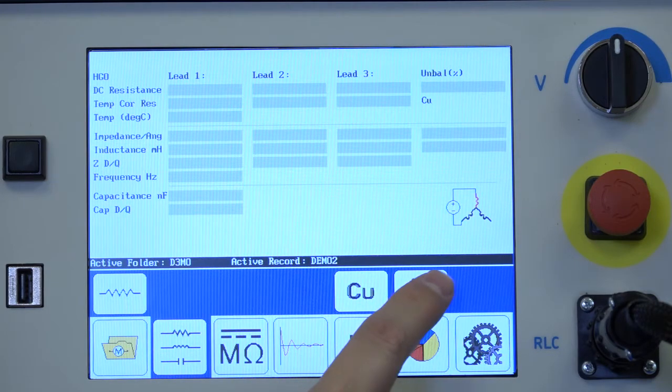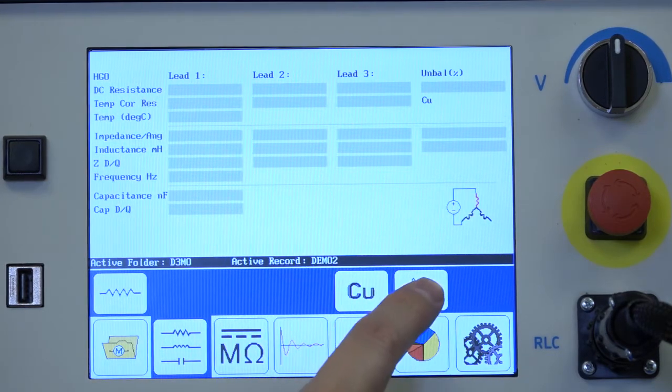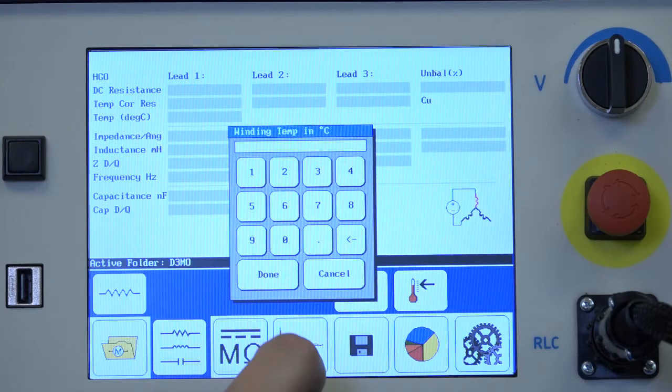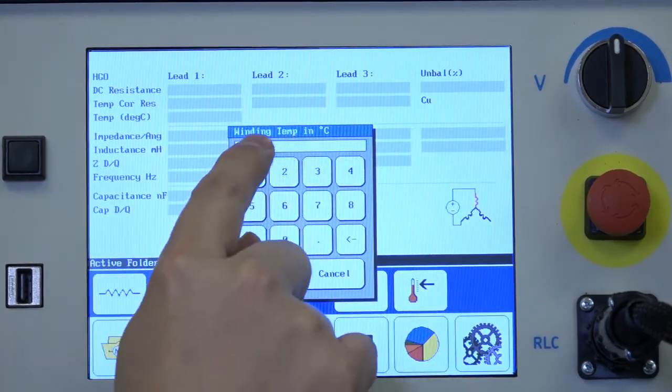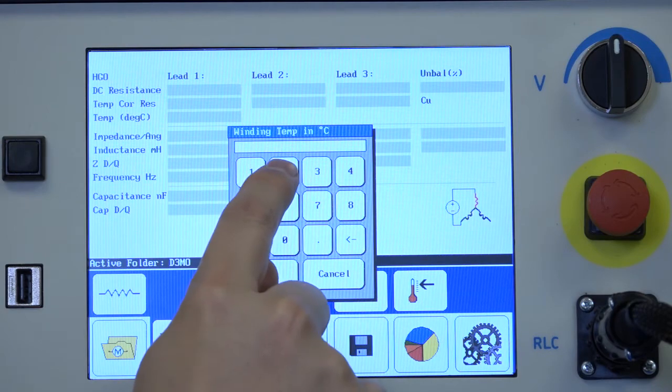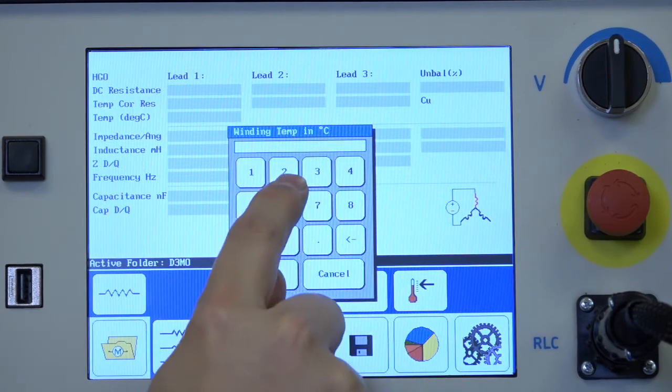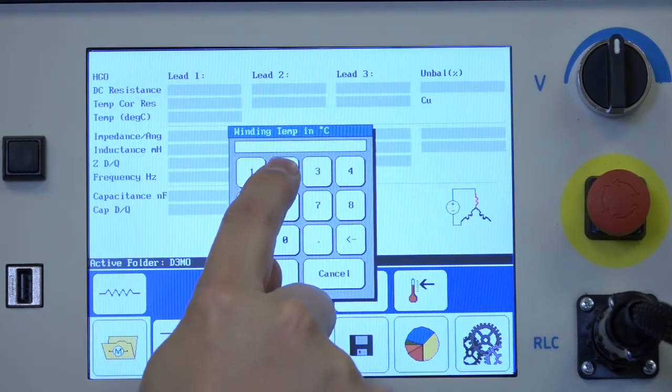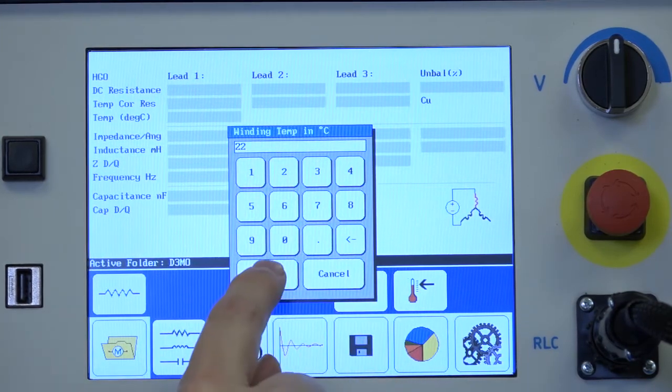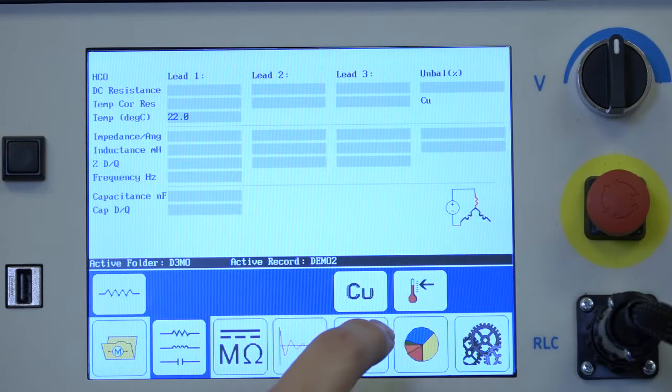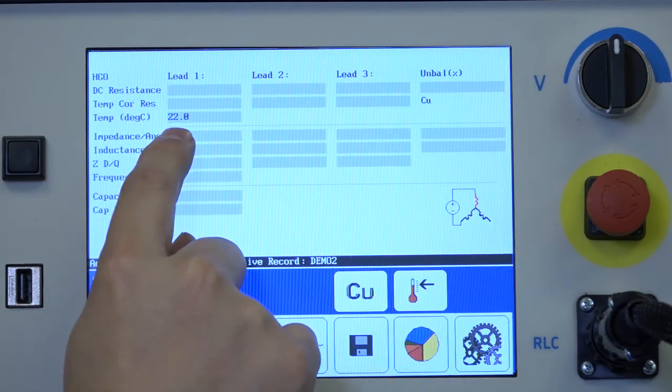And I also want to enter the temperature of the winding. So I'm going to select the temperature icon and enter my winding temperature. In this case I'm entering in degrees Celsius. That can be changed in the user settings option. My winding temperature is 22 degrees Celsius. Click done. Now that will be used for temperature compensation.